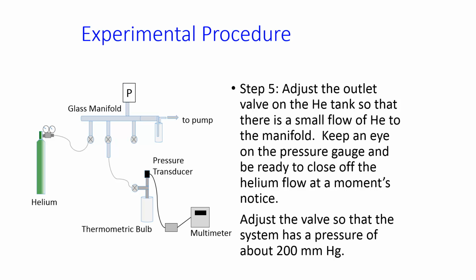When you're ready to add helium to your system, again, you're going to add helium first to the manifold, and then from the manifold to the thermometric bulb. You're never going to flow helium directly from the tank into the thermometric bulb. The manifold can handle it if you overpressurize it to a small degree. The thermometric bulb cannot, and the pressure transducer certainly cannot.